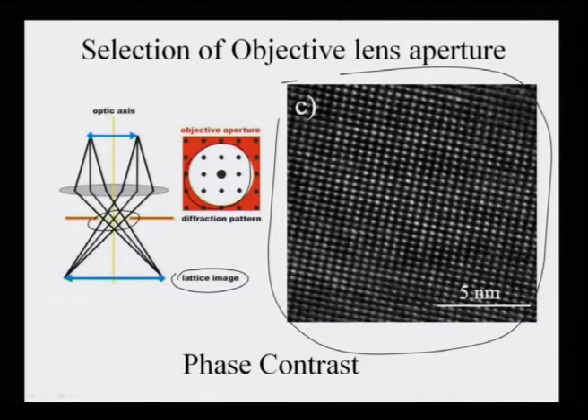In practice, by putting an aperture in the back focal plane of the objective lens, it is possible to form either a phase contrast or interference image — the interference of diffracted and transmitted electron beams — or to select one of the transmitted or diffracted beams and form diffraction contrast images. However, as I said, an electron microscope is not a perfect device. Any electron wave passing through the objective lens undergoes a phase shift and amplitude reduction — damping. Therefore we need to consider the transfer function of the objective lens to accurately describe the actual image.